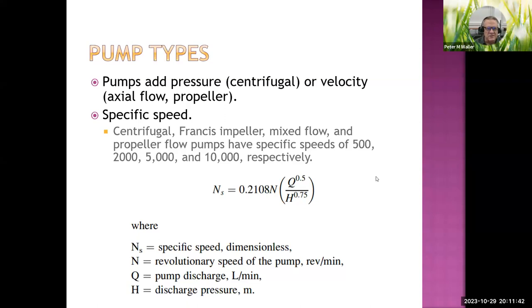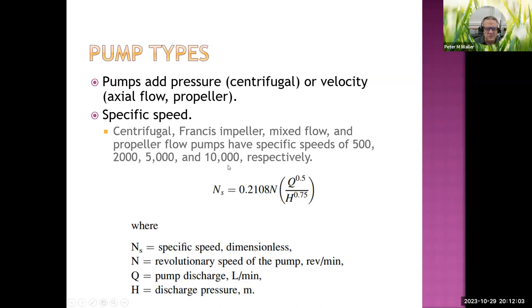Specific speed is the ratio of flow rate to pressure. Propeller pumps have a high flow rate-to-pressure ratio, so their specific speeds are in the range of 10,000. Centrifugal pumps at the other end have a low flow rate-to-pressure ratio, so their specific speeds are in the range of 500.